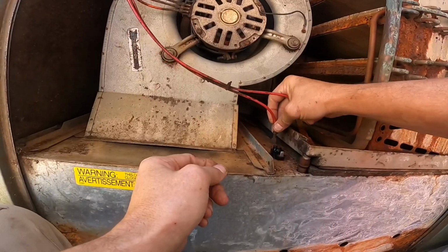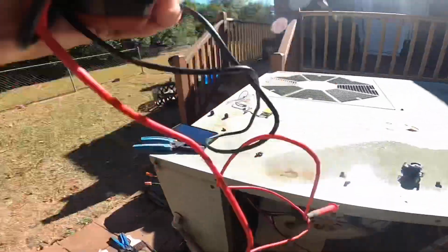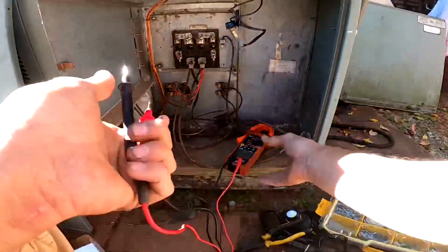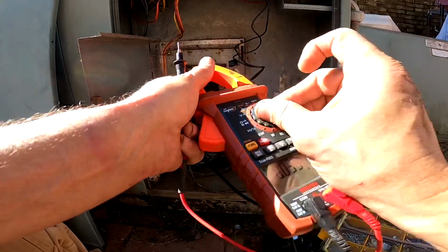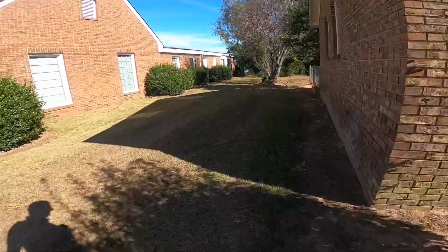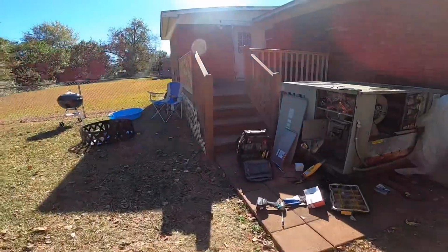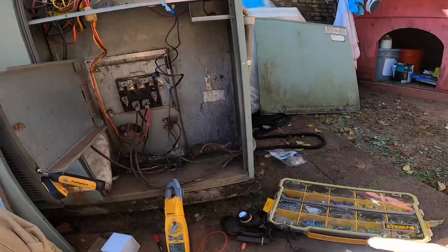All right. 26 volts. Hallelujah. Well, while replacing that one sequencer, the other one broke apart, so we are replacing them both with a 4-pole here. I don't need all these poles, but this is par for the job.